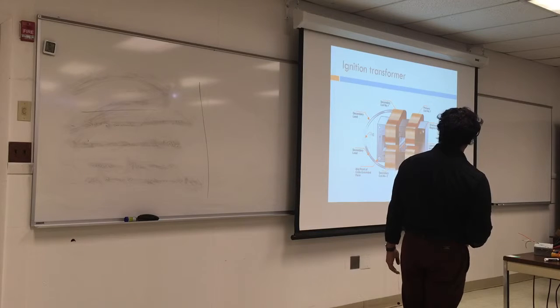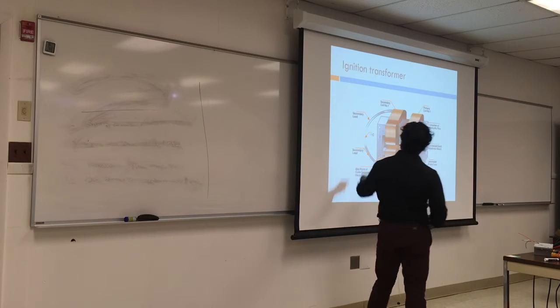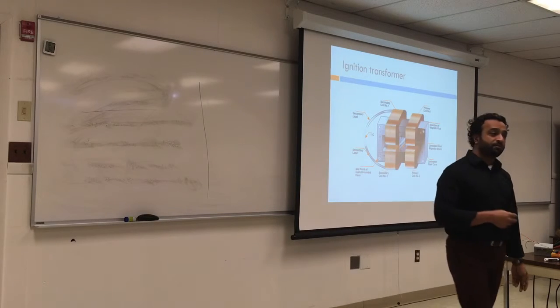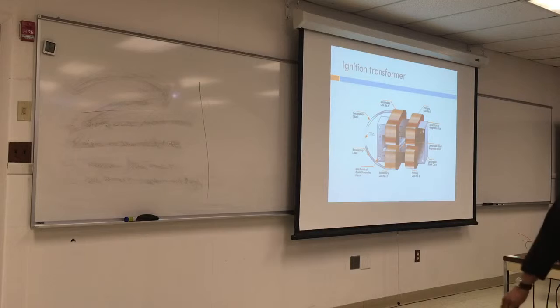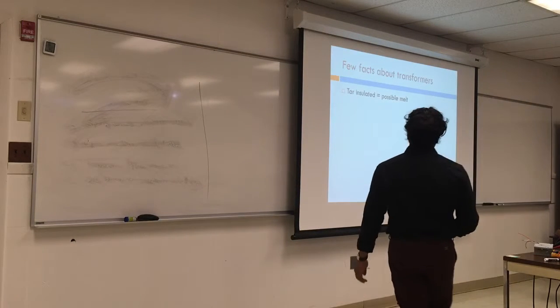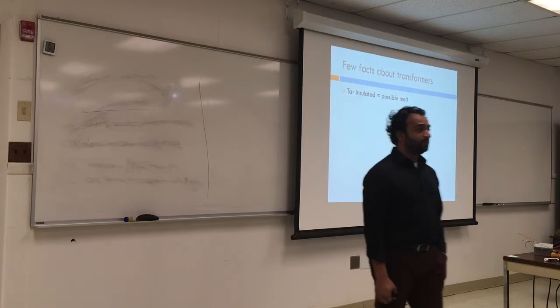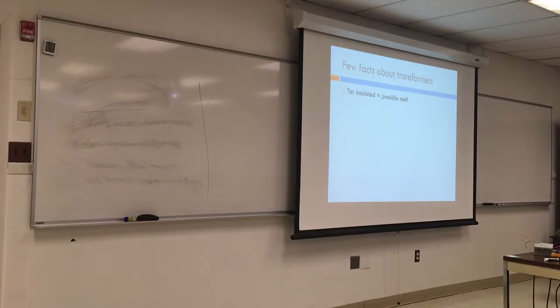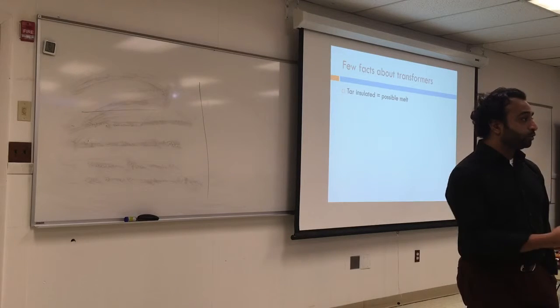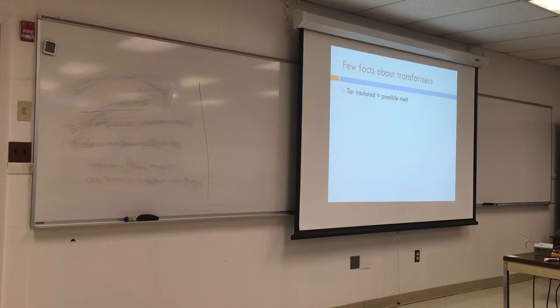Transformer: they have a secondary and a primary. This is the target we're trying to achieve, to jump the spark from one end to another. They are tar insulated, so they can possibly melt, and if they melt, they are not going to give you the right output. So when you install a transformer, make sure it's not in a hot place. How would that happen? Somebody installs a dryer next to the burner, and the dryer outlet is close to the igniter. Over time it will get hot, and the tar inside will melt or ooze outside, and that will not be good because the wires inside are supposed to work individually, not as a bucket.